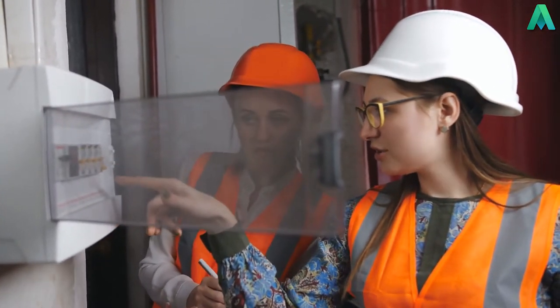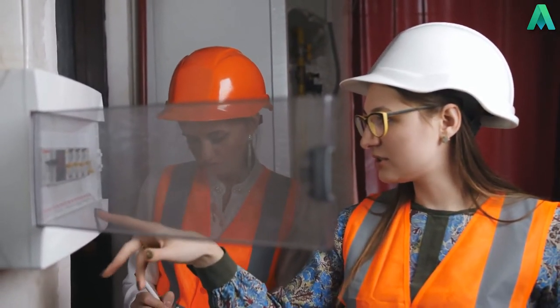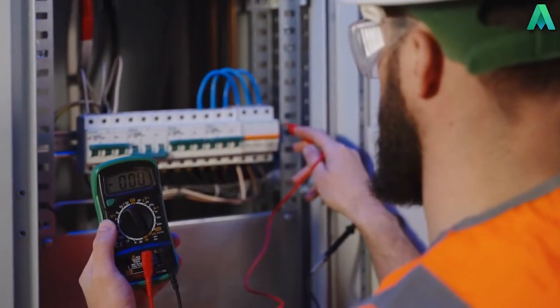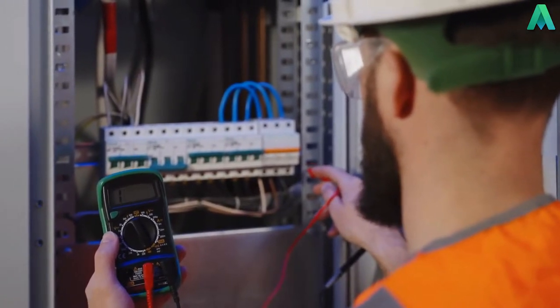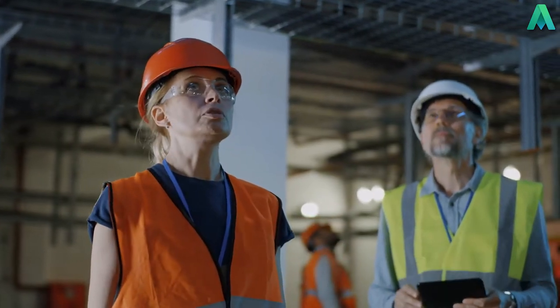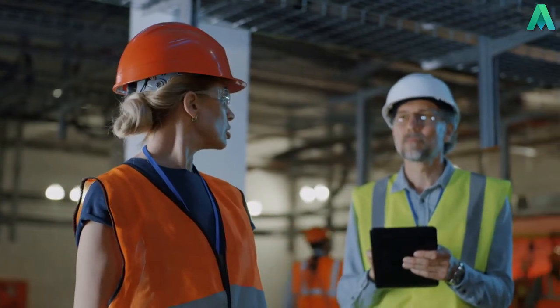This point is saying that when we do have equipment that requires calibration or verification, this is to be conducted against measurement standards traceable to international or national measurement standards. You might find that your equipment needs to be sent off to a certified tester to be calibrated at the required intervals. Using the multi-meter example, this would need to be sent to an accredited laboratory specialising in the calibration of digital multi-meters — you would normally see these laboratories accredited to ISO 17025. While you can check for general operation, wear and tear, or damage prior to use, you are obligated to send the device off to get calibrated at least annually, and this timeframe will depend on how and how often it is being used, so it could be more frequent as well.